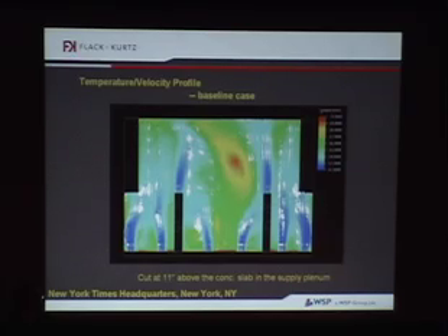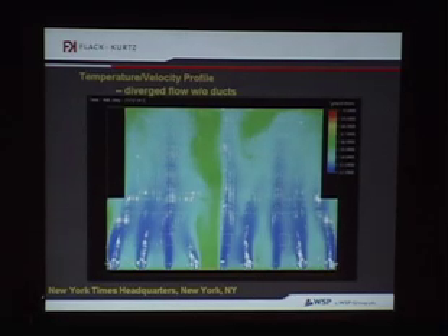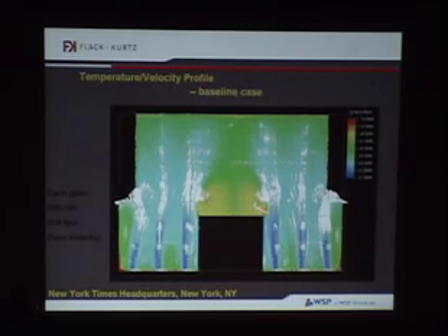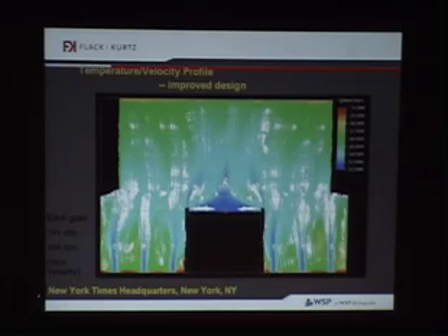And it warms up because of the heat below the floor. It's just an uninsulated concrete slab separating a warm plenum below that might be 80 to 85 degrees from the air under the floor that might be at 65 degrees. So it gets warm very quickly. So the key is to make sure that the underfloor air is set up so it's a uniform temperature and duration of time under the floor before it comes out. Similarly, we have areas of conference rooms and other things where we have slab-to-slab construction for acoustical privacy, and that creates shadows behind those obstructions to the plenum floor. So again, it was critically important to make sure we had the underfloor air plenum designed properly, and here we found out we did need some fingers to extend some things out. So while it's a ductless system per se, there is a minimal amount of ductwork going to the floor to ensure that that environment is actually properly distributed, and the space then actually takes care of itself.